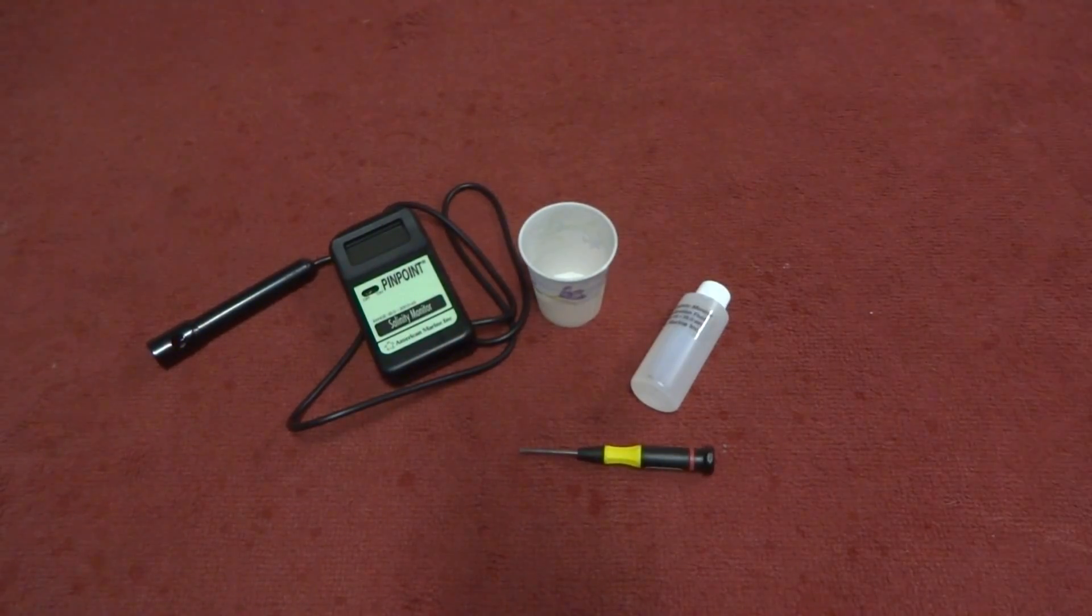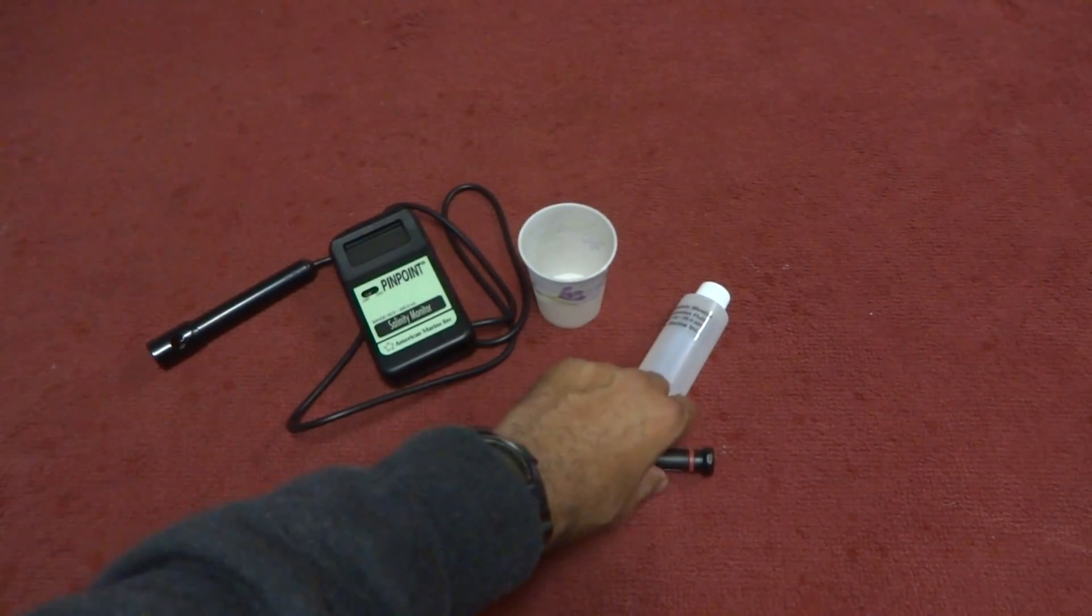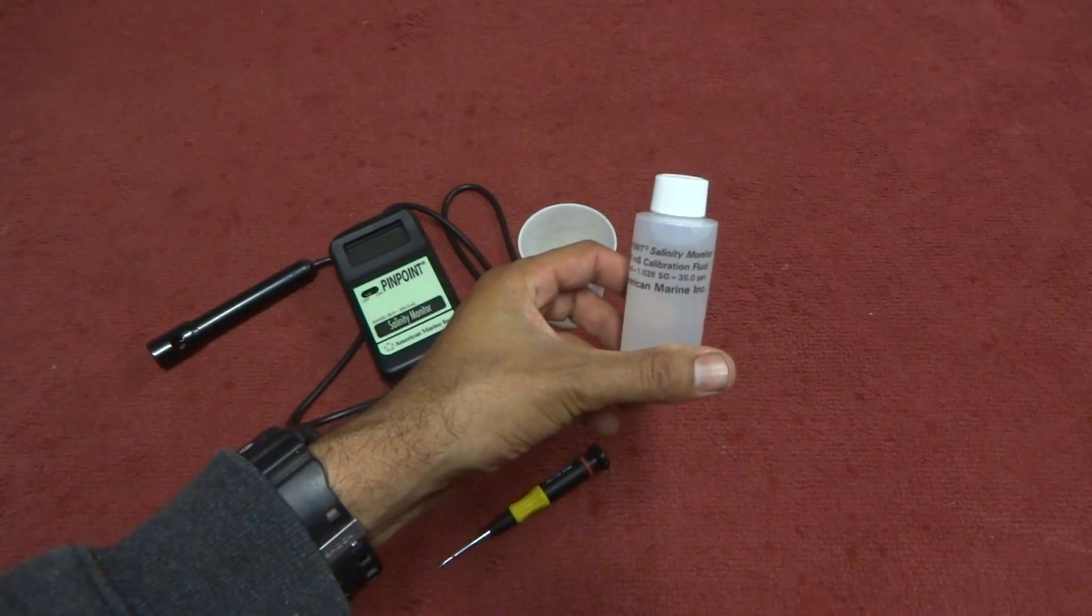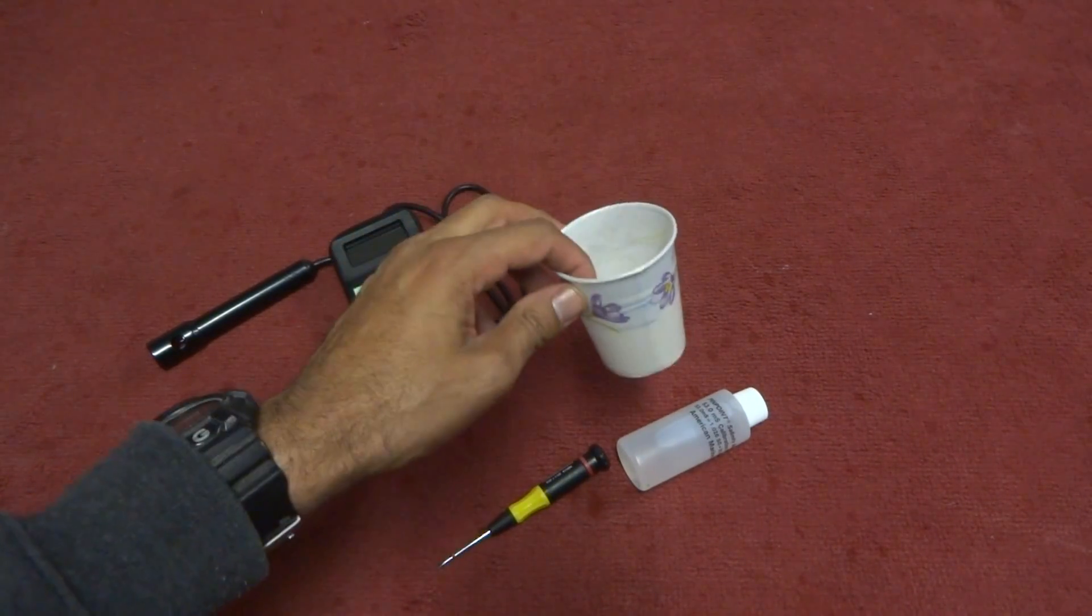These are the items you'll need to calibrate the salinity monitor. A mini flathead screwdriver, the calibration fluid, and a clean container.